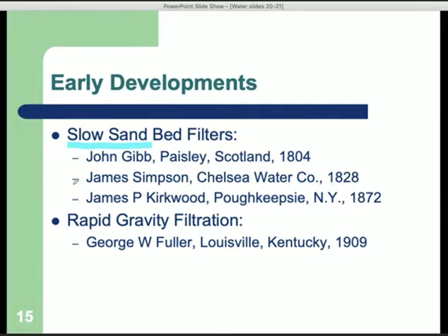That means if you imagine a sand filter, like on a nice beach sand, you look at a grain of sand, and anything that is about the size of the sand grain would possibly flow through a sand filter. So that means that sand filters are absolutely not able to retain bacteria or general solids, certainly not able to retain, say, pesticides or all these other modern pollutants that we have. For that, you would need the biological treatment that you had in the dirty layer on top of the sand filters. But these sand filters have gone out of fashion.